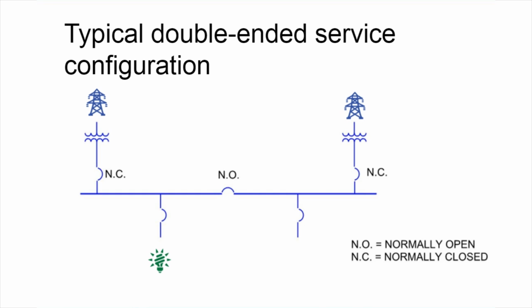Another approach might be to do two services coming in from the utility connected to a low voltage double-ended switchboard. Here we have a utility source feeding either half of the bus and all the loads associated with that particular bus. Then in an outage situation, you can automatically throw over to the other half of the bus so that all the loads are picked up from one side or the other.